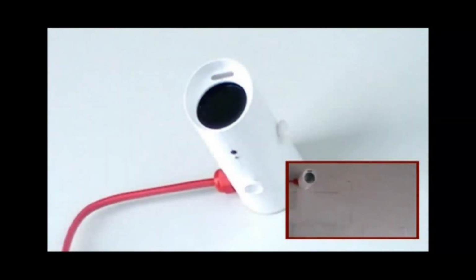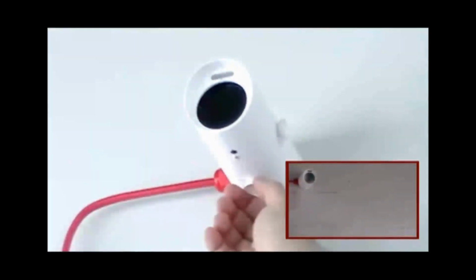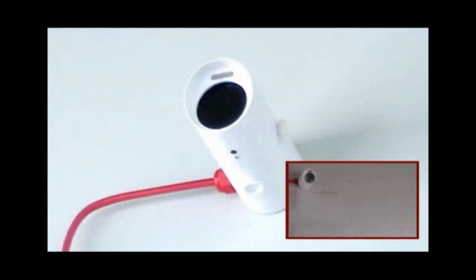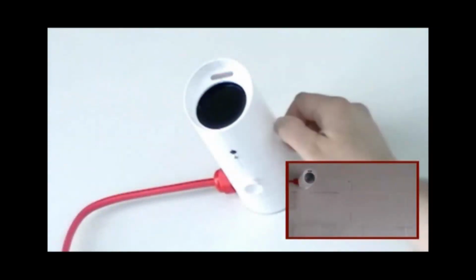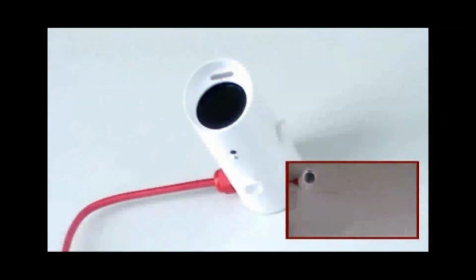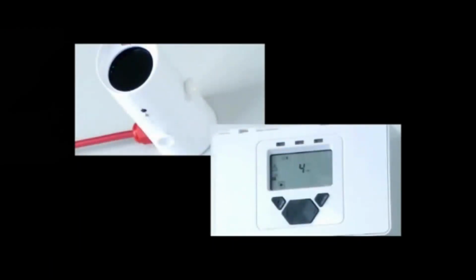We are going to use the thumb wheels to steer the laser in the receiver towards the transmitter. The laser is low-powered and flashes only once per second. However, it is a sensible precaution to avoid looking directly into it. It is not essential to steer the laser perfectly onto the transmitter. Within 15 centimeters is all that is required. If you cannot see the laser, refer to troubleshooting. Now that the receiver is correctly aligned, press the laser switch on the receiver or press cross on the system controller to turn the laser off and exit to the Engineering menu.